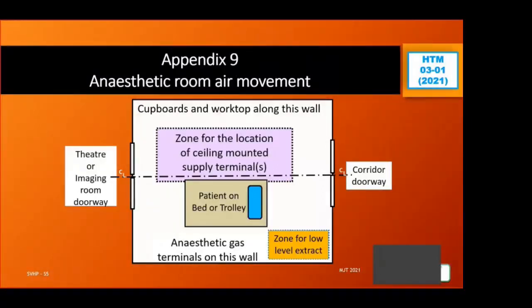I've put in Appendix 9, an addition about anaesthetic rooms as an example, showing where we put the supply terminal and where we put the extract terminal, to give a clean airflow path. Clean air comes out of the ceiling, past the anaesthetist, who's probably standing, past the patient, who's probably lying down, and down towards where the anaesthetic gas terminals are. That's probably where most of the waste or loose anaesthetic gas will be, because anaesthetic gas is slightly heavier than air and tends to sink if left alone. We want to encourage that flow and make sure we've taken all reasonable and practicable steps to protect staff from exposure to anaesthetic gas.